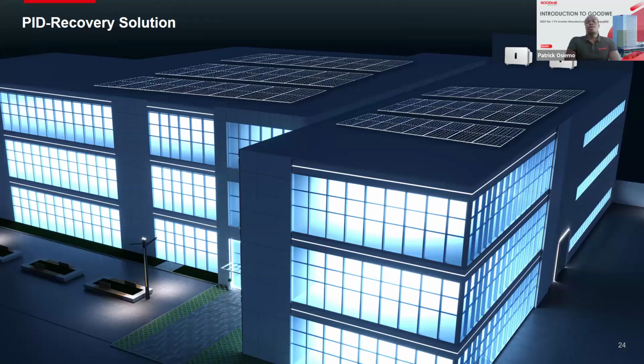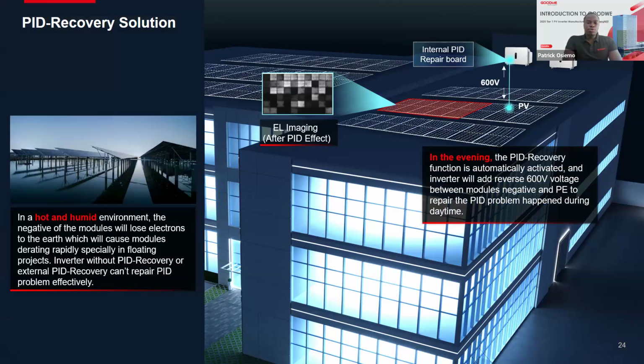Another protection feature that we have is the PID recovery, which is basically for installations or systems in very hot and humid areas. The reason being, your PV panels will degrade much faster if you're installing in such an area. With PID recovery, the inverter is capable of restoring the generation capacity of your panels by doing it overnight, restoring the generation of your panels to the way it was before.